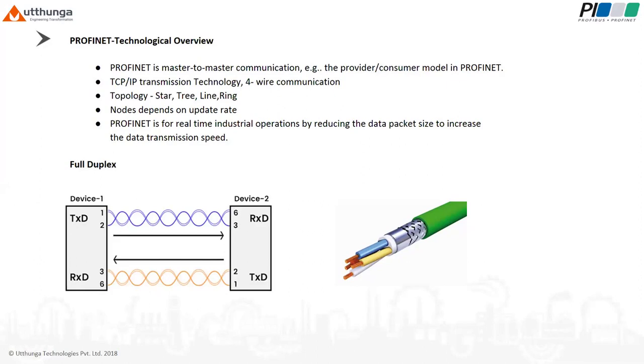For instance, I can say that two very useful technologies are built into PROFINET. Like if gigabit communication is running and a cable is cut, it will automatically go to full duplex communication. Gigabit means 8-wire communication. If some cable is damaged, then it will go for full duplex communication. Full duplex means 4-wire communication. This technique is known as auto negotiation. And also if I change the send and receive wires, it will still work. This is known as auto crossing. These two techniques are really valuable in plants. Moreover, in PROFINET, we can achieve star, tree, line, and ring topologies. That is the flexible topologies of PROFINET.